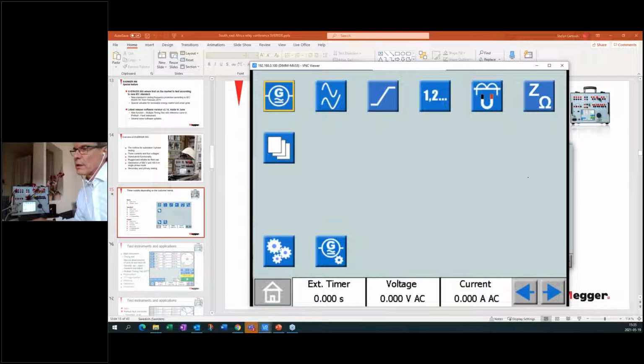So you can see my screen, and I have a very small spot here, but I hope you see that black square. Now you can see all six instruments here. Here you have the file manager, and here you have the system configuration where you set the date, time, and so on, and also language, the general settings when you first receive the Sverker 900. And here you have the settings of the generator. If you would like to go to single mode and connect the voltage or current output in parallel or series, then you go to this symbol.